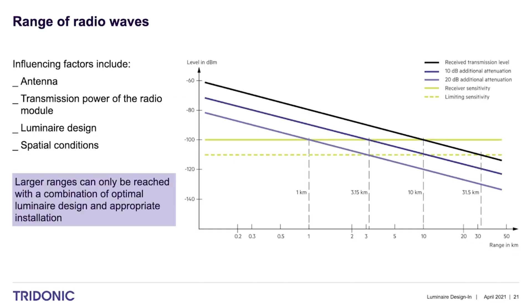Now to the installation of the radio components in the luminaire. The correct placement of the radio components is essential. The following points can influence signal quality and must be avoided: enclosing the radio components with metal, which leads to a Faraday cage; insufficient distance between the antenna and metal parts; and shadowing of the radio signal by metal parts.